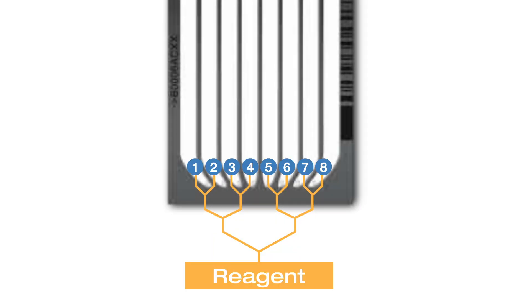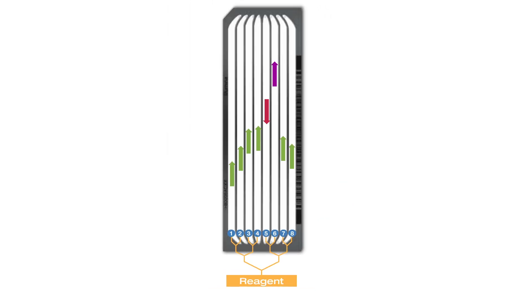Backflow can result due to the binary splitting of reagent lines. Lanes 1 and 2, 3 and 4, 5 and 6, and 7 and 8 share a direct connection just before where the reagent enters the flow cell. A blockage in one of the lane pairs can cause the pull of liquid in reverse towards the inlet port through the binary split and back through the flow cell through the partner lane. In this diagram, lane 5 shows backflow while lane 6, its pair, shows faster than normal forward flow.